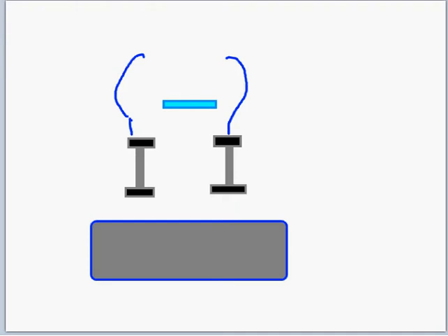And the way electrons are going to work here is that they come down in kind of a pencil beam, a very thin beam coming into this scattering foil, and then they're scattered off of this thing just to spread out the beam a bit, and they get collimated or absorbed by the collimators you've got hanging down at the patient.